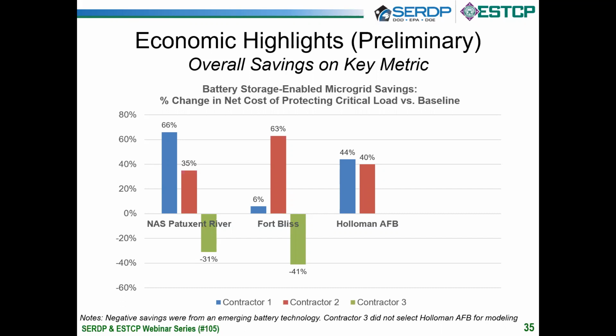You can see that the same two contractors had similar results at Holloman, where there were 44% and 40% savings achieved, which were material there. At both Patuxent River and Holloman, the savings originate from multiple sources, and this is important to understand. This is not a case where a battery is installed, it does one thing well, and that drives the economic case. There's a number of different areas where the addition of that to the microgrid can drive value. Retail bill savings, reduction in the number of diesel generators, in some cases reduction in the number of UPS, in addition to potentially extra revenues from PJM wholesale market participation for the Patuxent River base. A comparison set of results from NREL is on the next slide, 36.